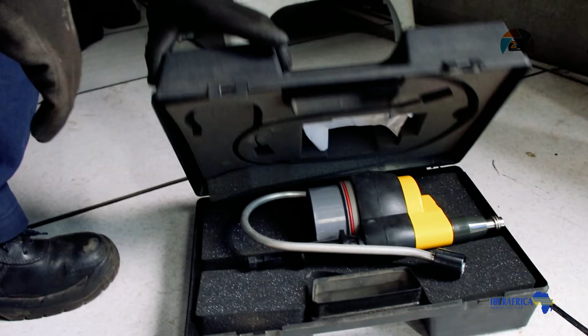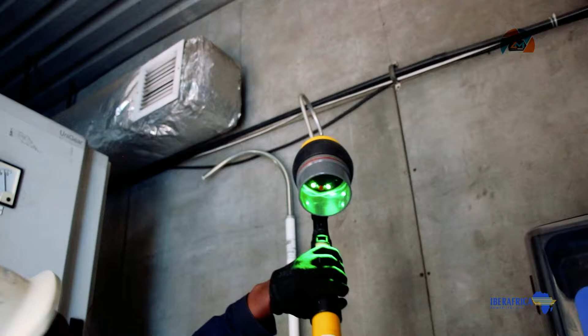For the testing of the voltage along the bus bars, we have a tester which is connected to the telescopic insulated rod. But before starting the job, you also have to test the tester itself. Secondly, we have the earthing equipment. It's our CME. When we want to perform these jobs, sometimes you need to verify if the PPE you are using is also in good condition. For example, if you are working with a rubber glove, just do an air test. Just bring it near to hear if there is any air leaking. If it's in good condition, it's good for you to work with it.